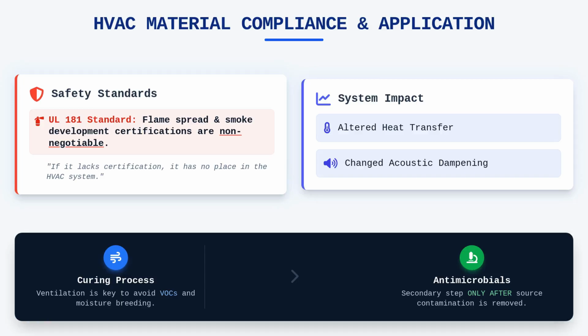Furthermore, managing the curing process is essential. You must ensure adequate ventilation through the system to speed up dry times and prevent the accumulation of volatile organic compounds. Leaving a duct damp after application creates a potential breeding ground for moisture-related issues, which is exactly what we are trying to avoid. Using antimicrobial coatings can be a valid strategy to inhibit future microbial growth. But this is a secondary step that must only occur after the source of the initial contamination has been fully removed.